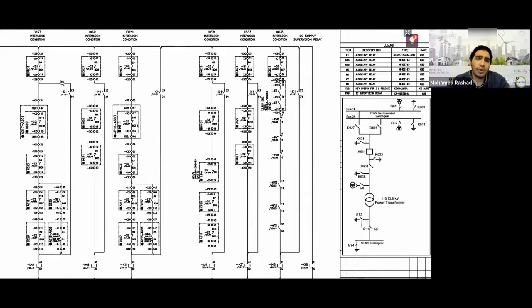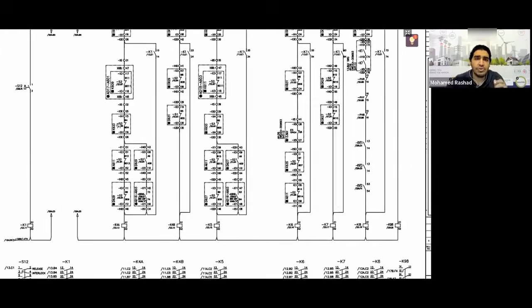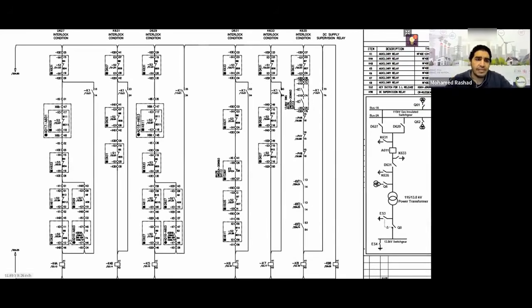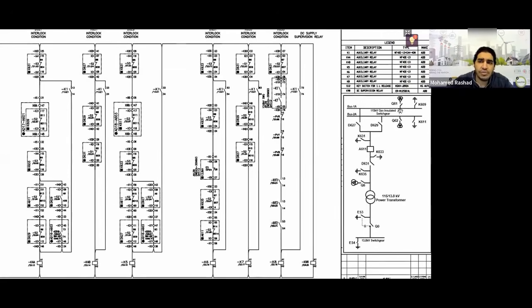All right, here you have something called a bypass isolator, an interlock bypass, which is key 1 that I mentioned to you. If you activate key 1, it will bypass the entire story I told you about and directly activate the contactor or the auxiliary that indicates the interlock is fine for you. When it goes down, where does it go? To the panel here. This panel contains the earth switch, which is key 389. This earth switch is located on the bus bar, not associated with a specific cell, which is why its wiring is installed in a specific panel, right? Make sure the bus bar is open, then go down and take key 633, which is open.